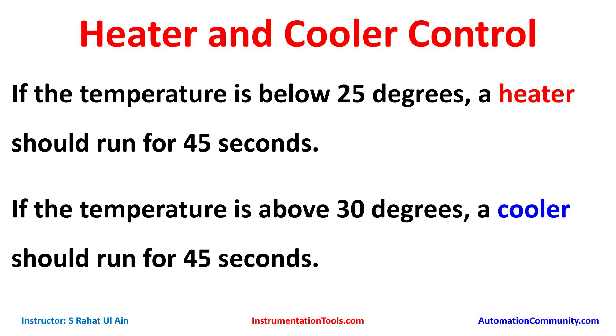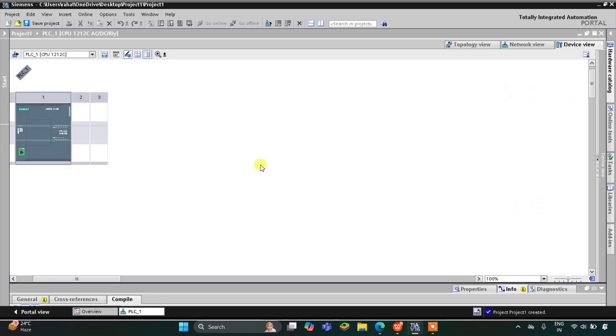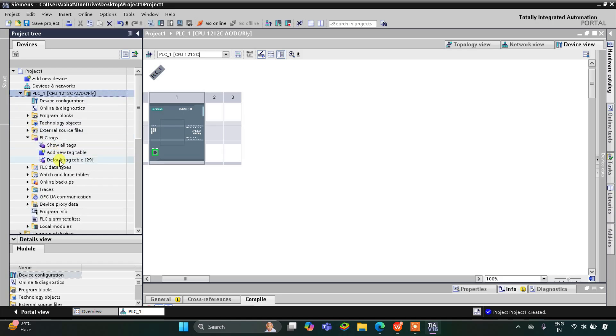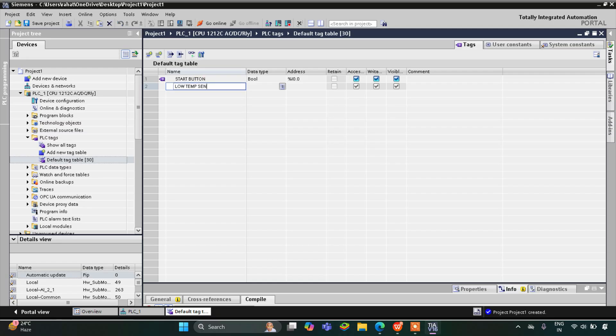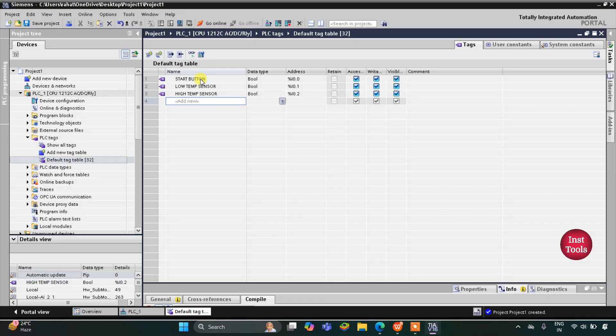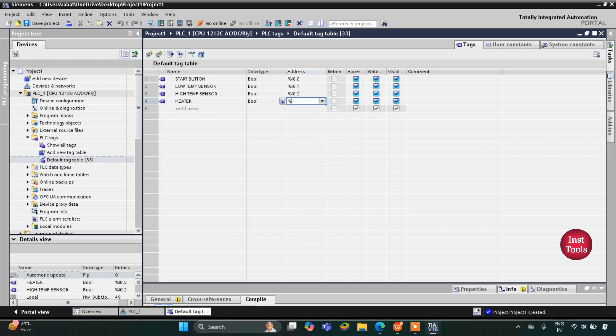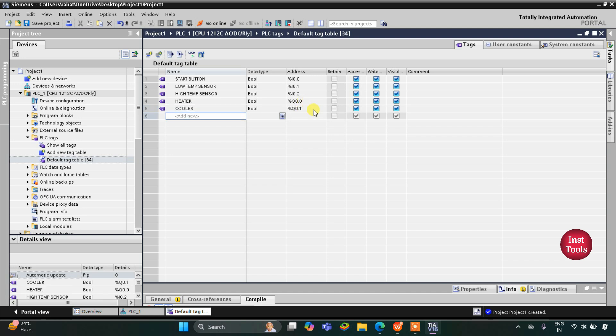Let's move to TIA Portal where we will draw a ladder diagram for this heater and cooler control example. This is the interface of TIA Portal version 16. First we will go to PLC tags and the default tag table. Here we need to add our inputs and outputs. We have inputs like start button, low temperature sensor, and high temperature sensor, and two outputs: heater with address Q0.0 and cooler with address Q0.1.